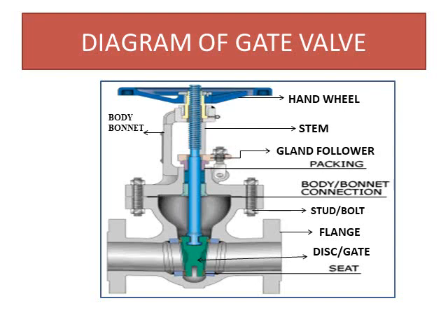Here you can see gland packings are provided to prevent leakage from the valve to outside along the stem. So this is a gland follower which is tightened by eye bolts. So these gland packings are always under pressure to stop the leakage along the stem.